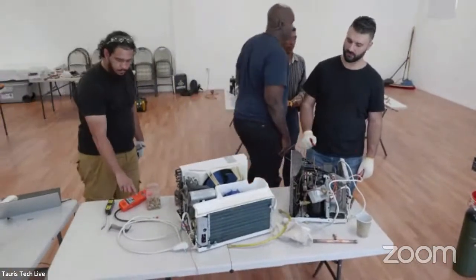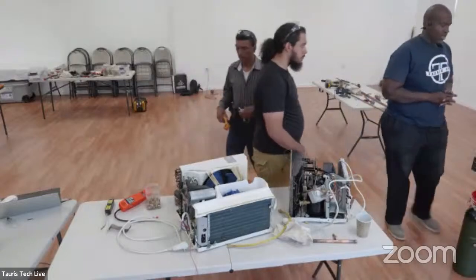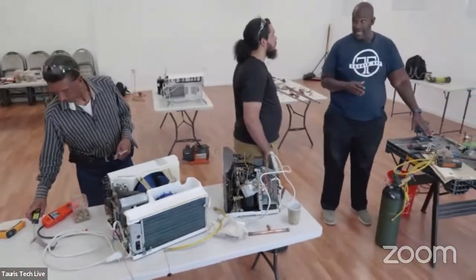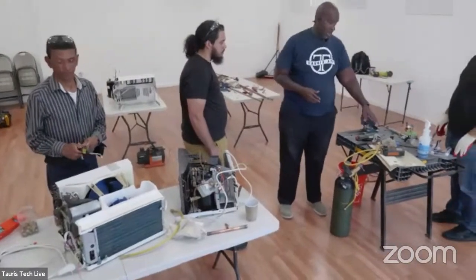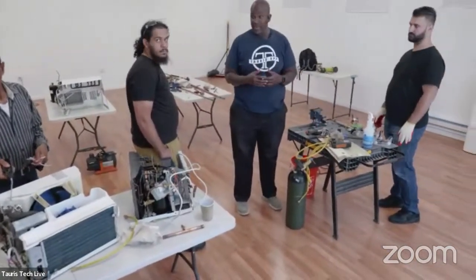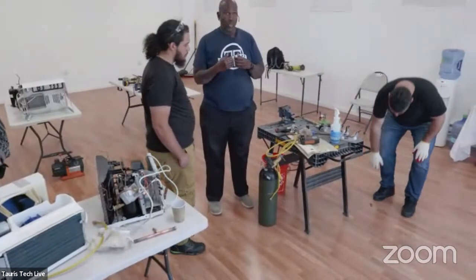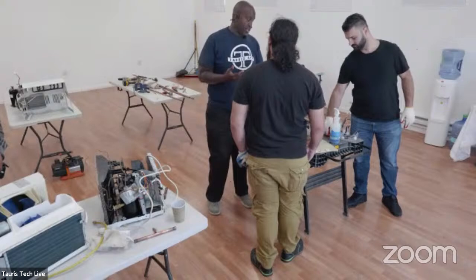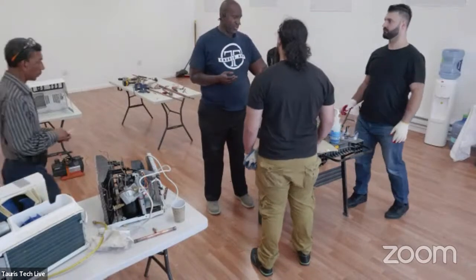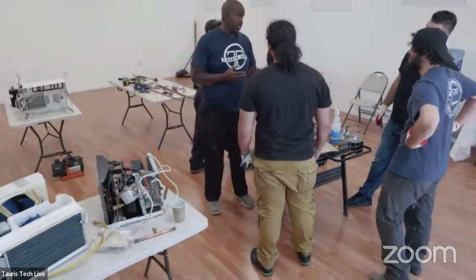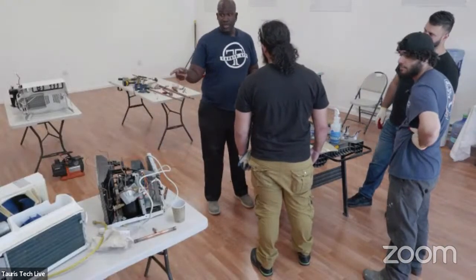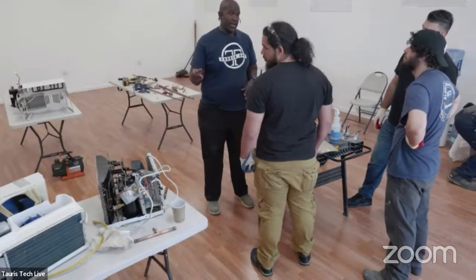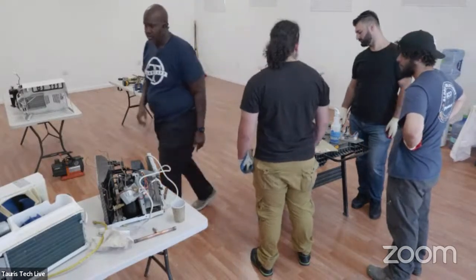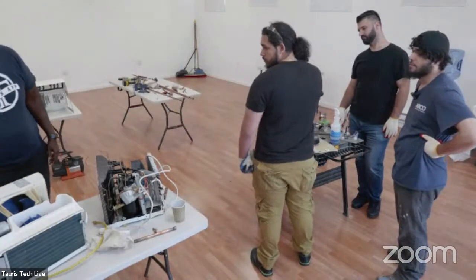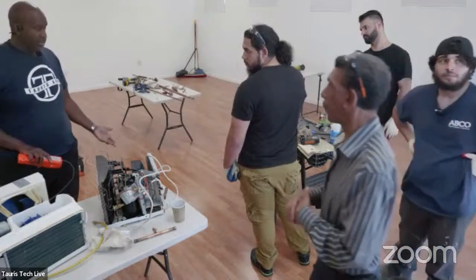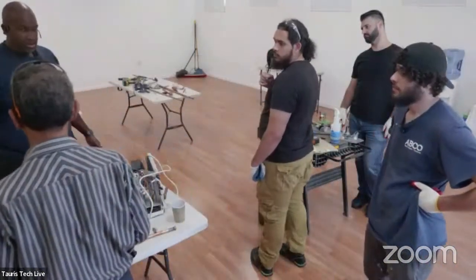In terms of leak testing, there's two things you're trying to figure out. Is it leaking? And then where is the leak? If the pressure keeps dropping here, then it's telling me it is leaking, but it's not telling me where. There's a couple of ways you can do it. You have your bubble spray. If you see a bubble, there's a leak at that location. You can use an electronic leak detector. If I sniff here, there's no leak there. There's a leak right there.